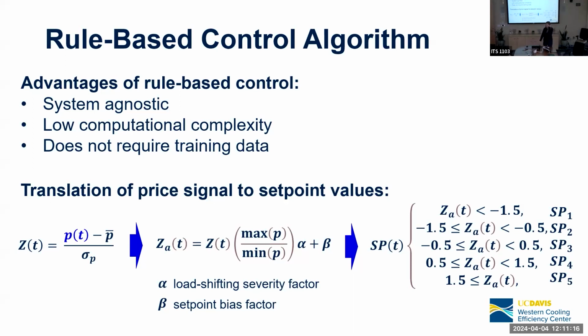There's a question. Oh, what's the question? You want questions while you're going through? Sure. Is the bias, for example, in winter, you want to bias it towards the heat of the space, whereas in summer, you want to bias it towards the cooling of the space? Is that why there's a bias to those set points? Yeah, it could, I mean, that's one application for that. Alternatively, if you have a particular preference from a customer on having maybe a warmer space than a cooler space, you could skew the set points a little bit higher just to take into account thermal comfort of that particular person. Yeah, it's kind of case by case how you want to handle it.